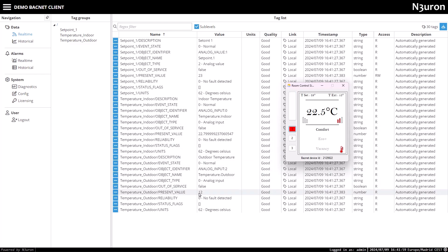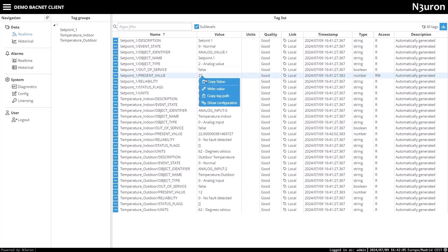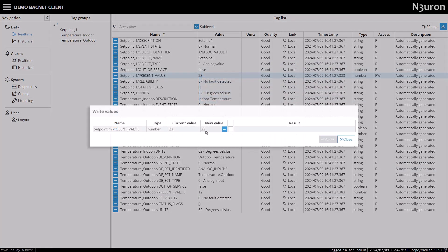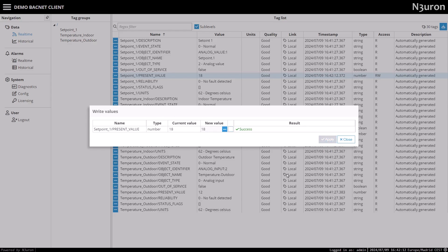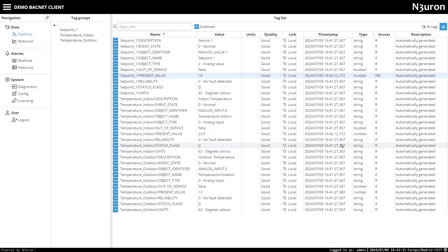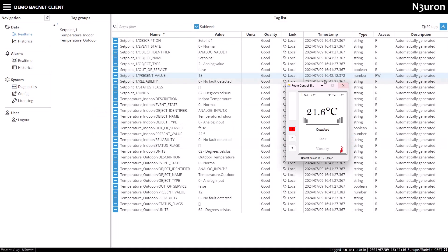To demonstrate a real use case of controlling room temperature, I'll write a new setpoint value for room 1 by selecting setpoint1's present value. For this example, I'll set it to 18 degrees and observe the temperature decreasing to reach the new setpoint.